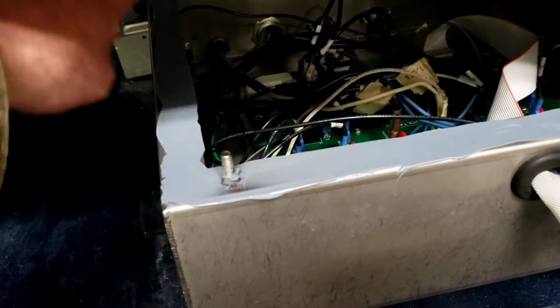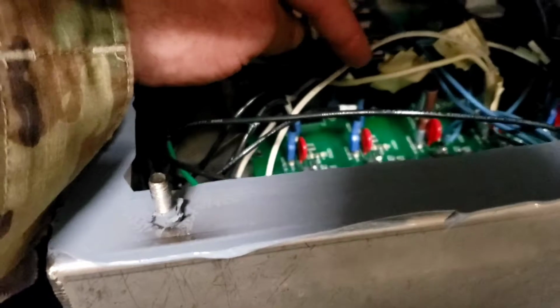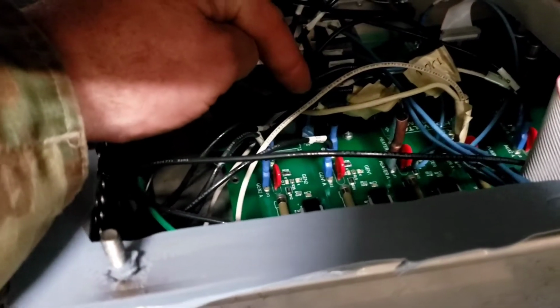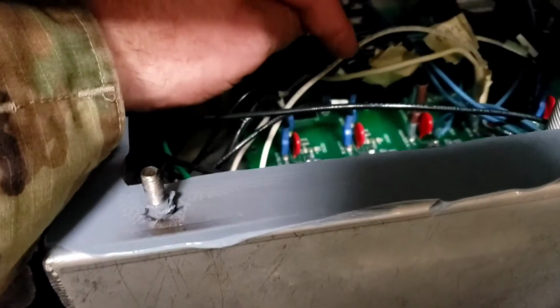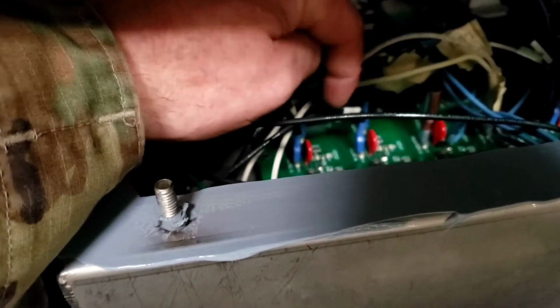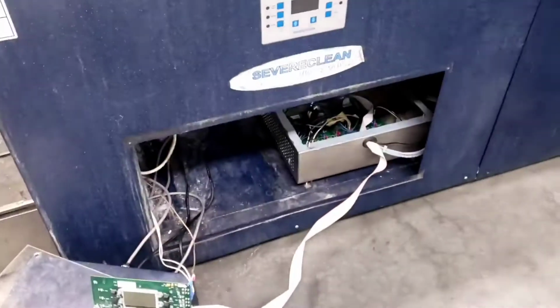So then we're like, okay, is there an issue with the receptacle? The receptacle has 120 and 120 going in to get your 240, because this whole board is 240 volts. We're going to swap Gen 1 with Gen 2, both 120 leads, and that'll show if our fault stays on Gen 1 or if it moves, and we'll go from there.